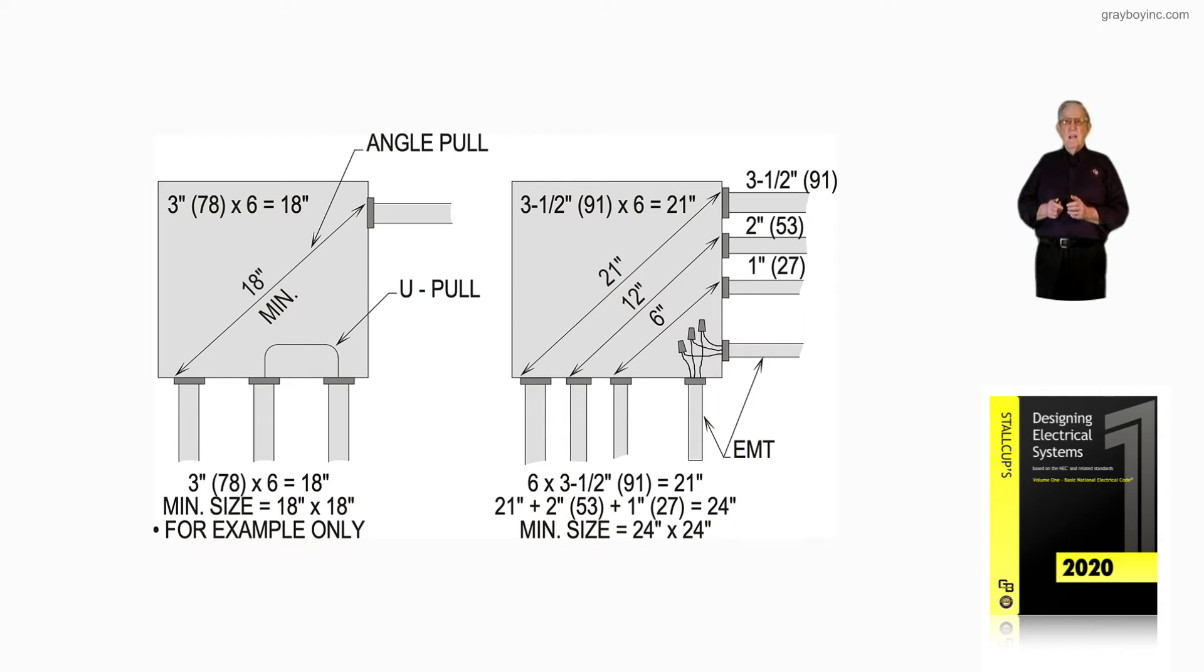Notice we have 3½, 2-inch, and a 1-inch. So the code requires that we take six times the largest, 3½, and add that to the remaining conduits on that wall. So you would have 21 inches plus 2 plus 1, giving us 24 inches.